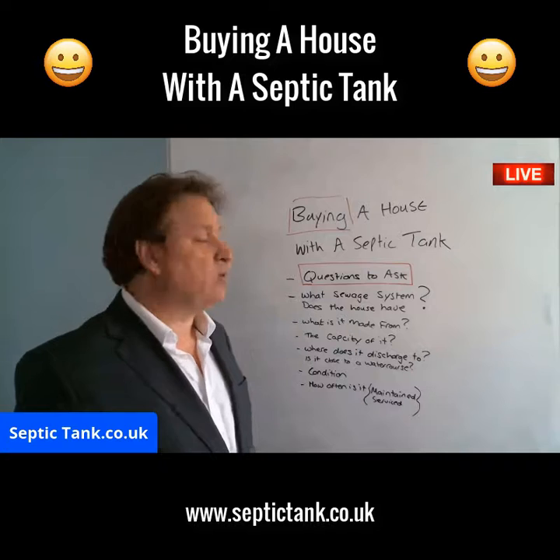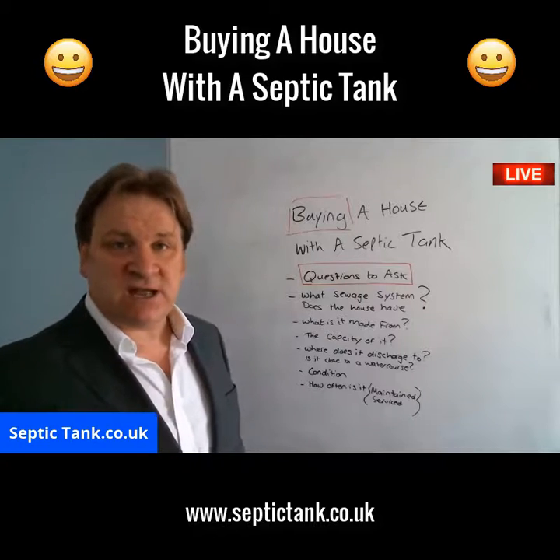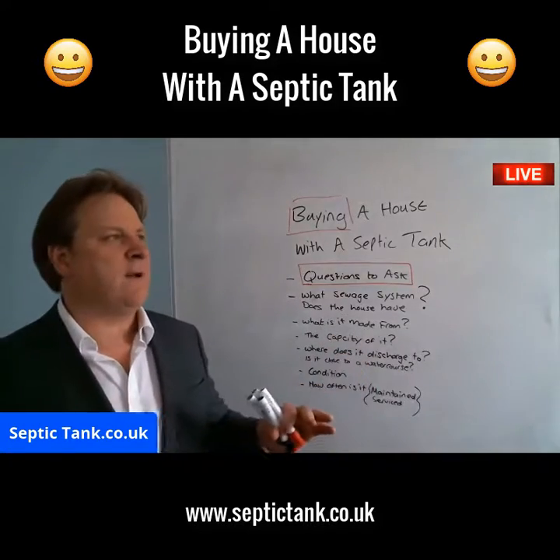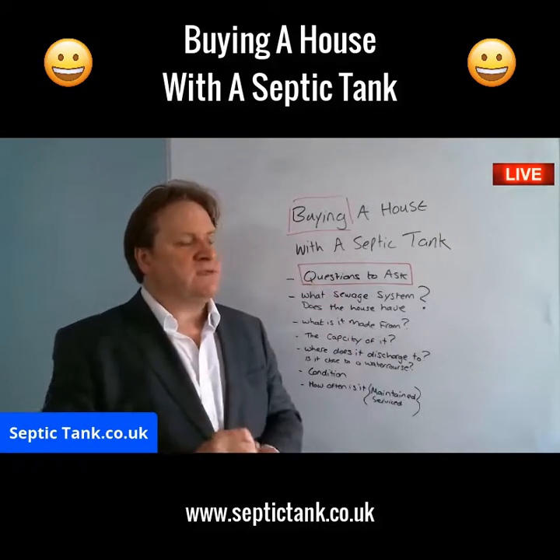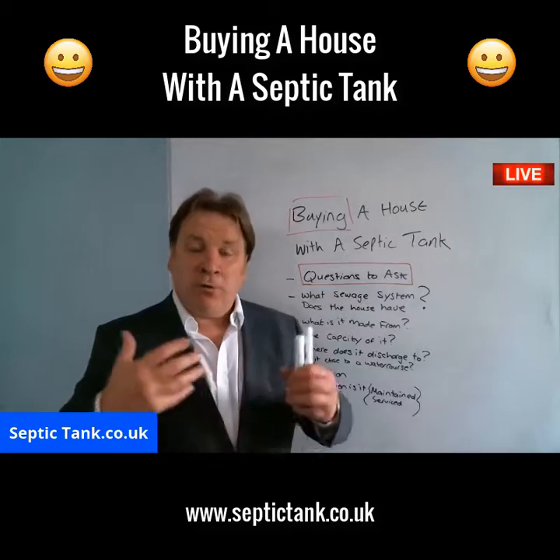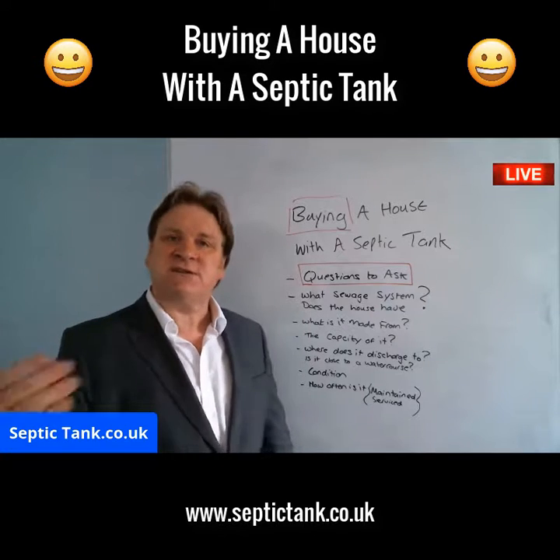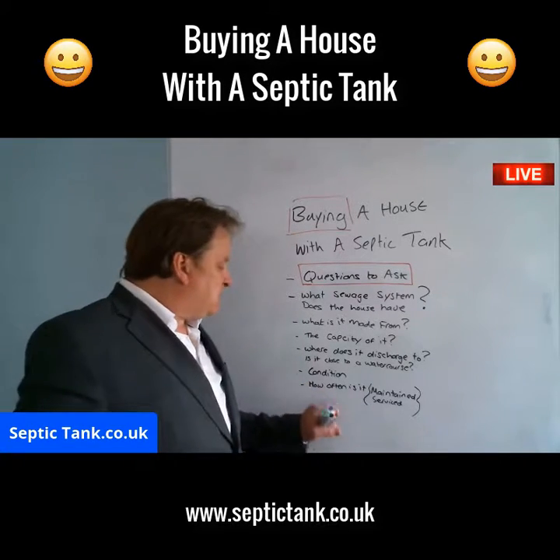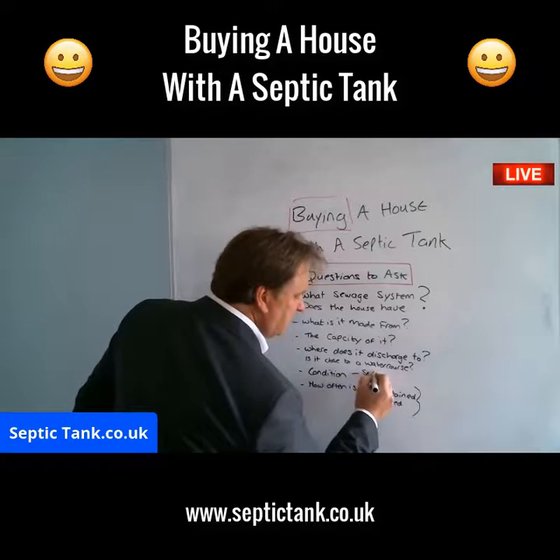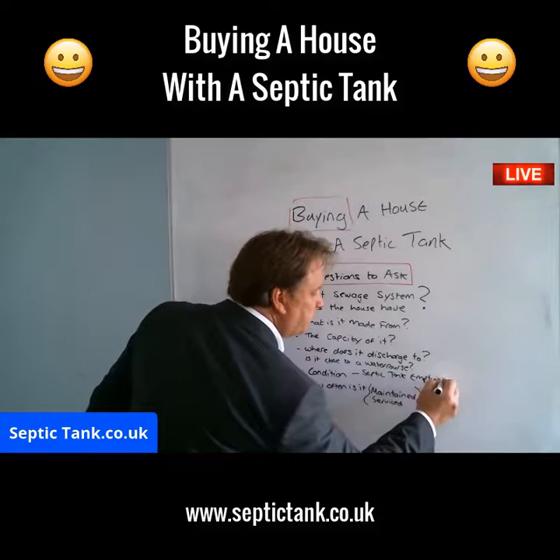And that's very, very important because septic tanks should be sucked out or desludged every year. Some people lift their lid and see the septic tank's full of water and they think, oh my gosh, we've got to get it emptied. No, no, no, it doesn't work like that. A septic tank is always full of water. That's how they work. They're always 3/4 full or more. Now, what we're saying is over the course of the year, all the fat and the grease and the sludge build up in a septic tank. And that sludge and the fat and the grease has to be sucked out and desludged once a year. So you can ascertain how well they've maintained it by septic tank emptying receipts.